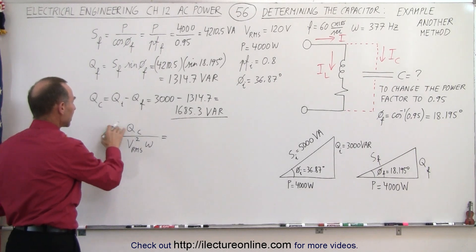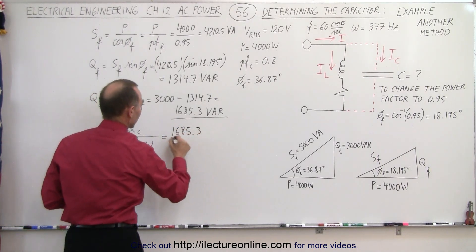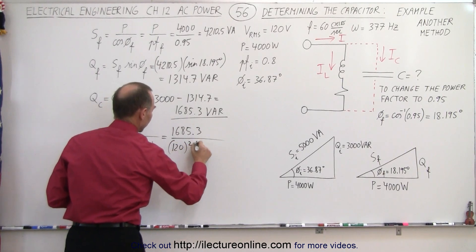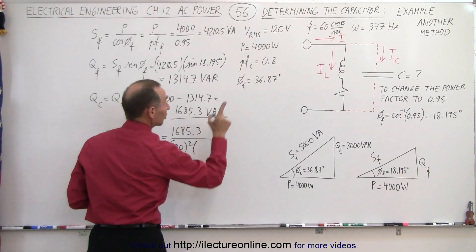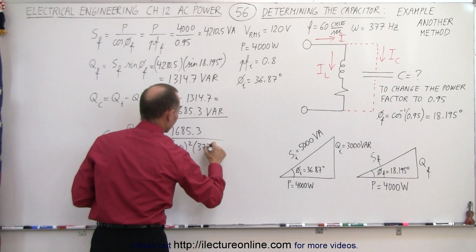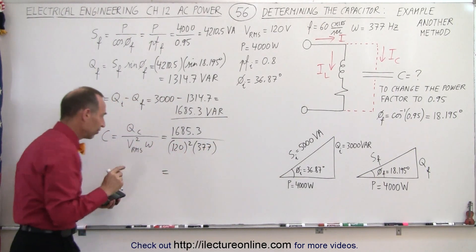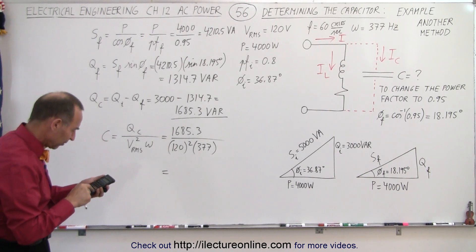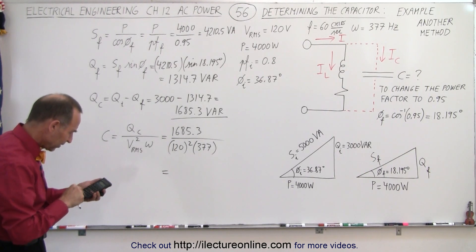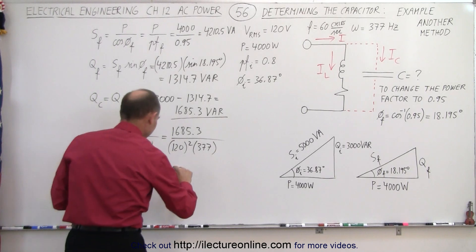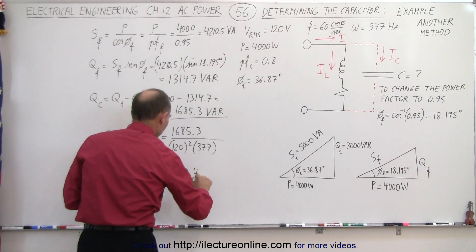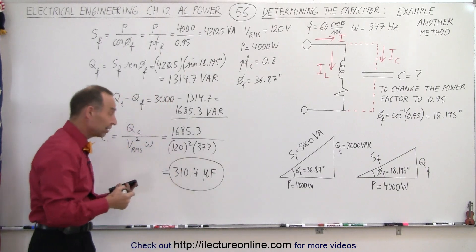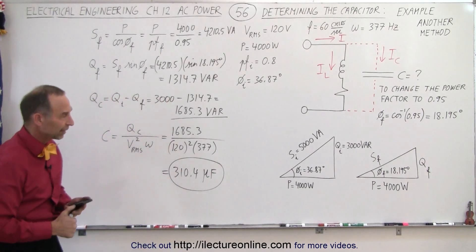Now we plug that in here and divide it by VRMS squared times the angular frequency of the circuit, which is 377. And that gives us the new capacitor value. So divide by 120 squared and divide by 377 and we get 310.4 microfarads, which is the exact same value that we got in the previous video using the different method.